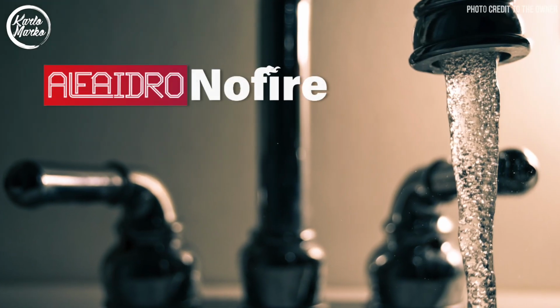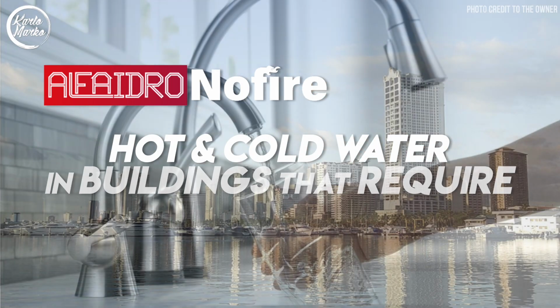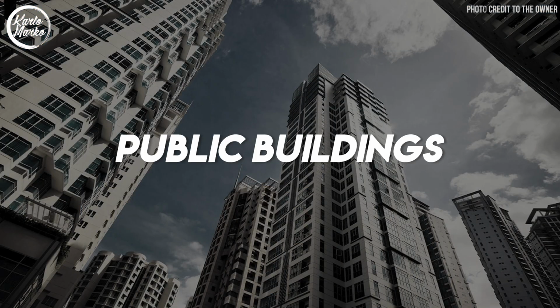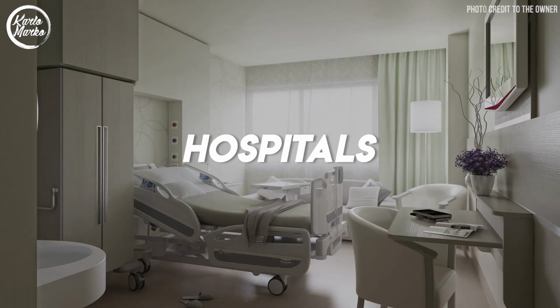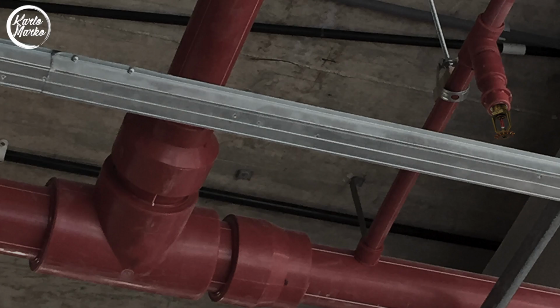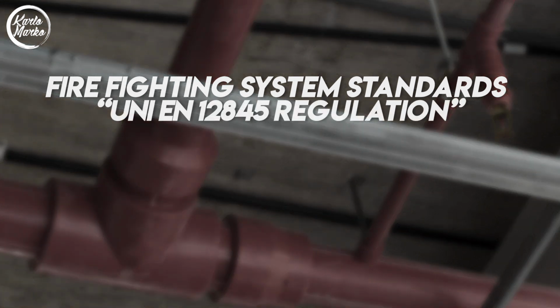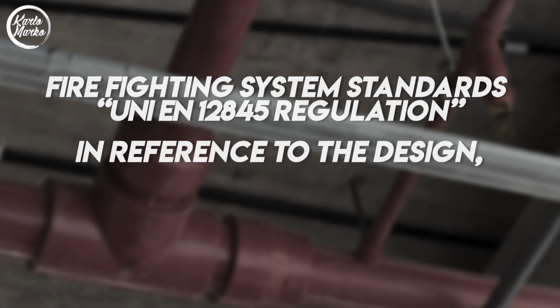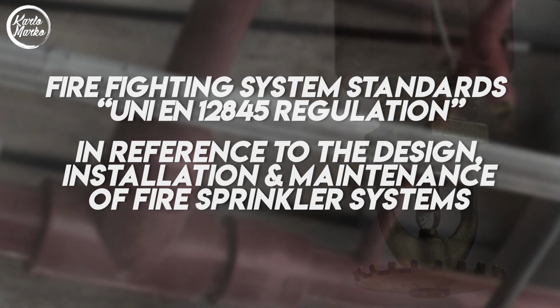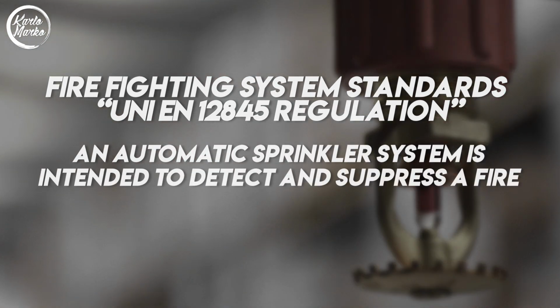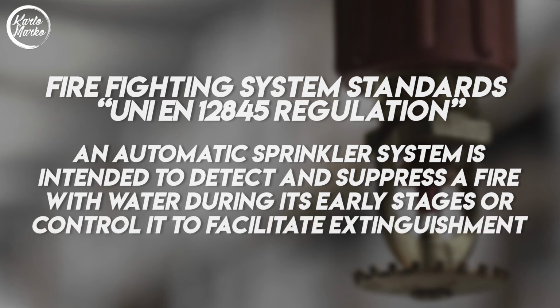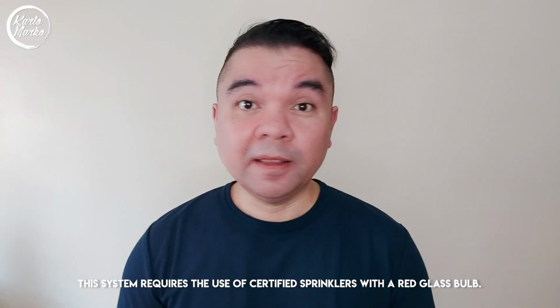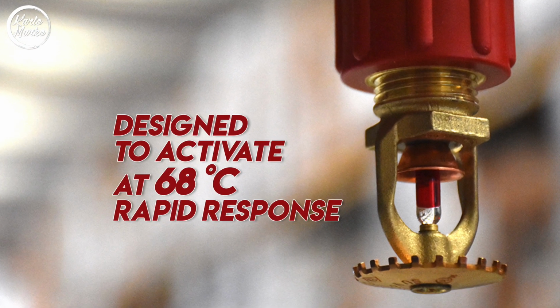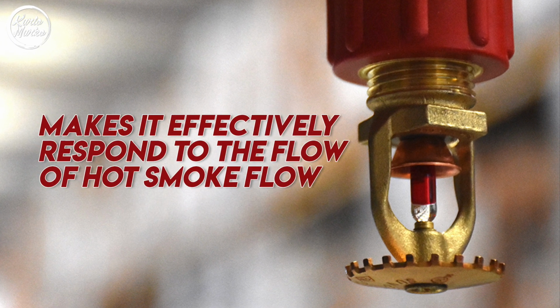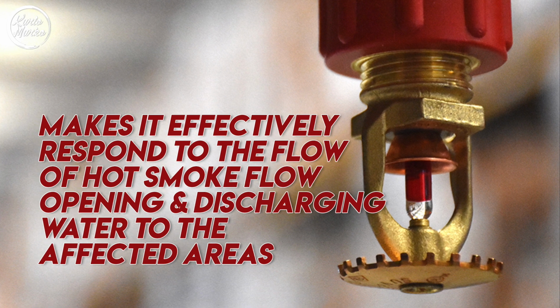The Alfaidro No Fire system is also suitable for transporting hot and cold drinking water in buildings that require fire resistance, including public buildings, hotels, vessels, caravans, shops, hospitals, schools, museums, and private buildings. As per the firefighting system standards or the UNI EN12845 regulation, which serves as a reference for the design, installation, and maintenance of fire sprinkler systems, an automatic sprinkler system is intended to detect and suppress a fire with water during its early stages or control it to facilitate extinguishment through alternative methods. This system requires the use of certified sprinklers with red glass bulbs. These sprinklers are designed to activate at 68 degrees Celsius rapid response. This makes it effectively respond to the flow of hot smoke flow, opening and discharging water to the affected areas.